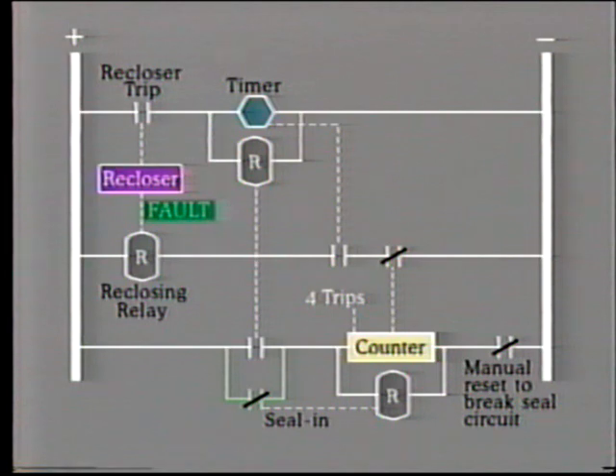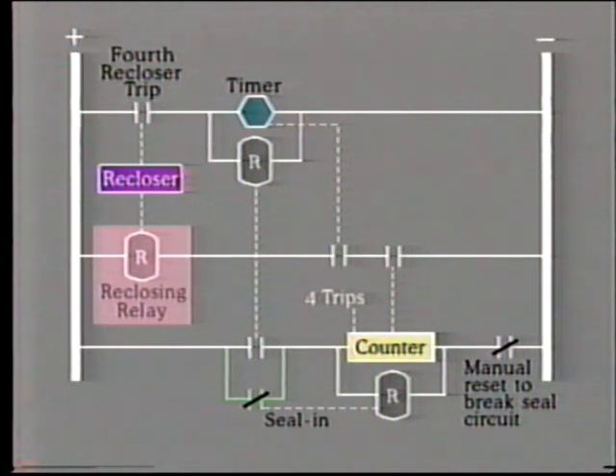If the fault still exists on the feeder, the recloser will trip again and repeat the sequence. On the fourth trip, that is after 3 reclosures, the counter output is energized, so opening the normally closed contact. This prevents further reclosure until the fault has been cleared and the control circuit reset. To do this, the recloser is switched to manual control and the counter seal-in contact is opened, so returning the circuit to the start condition.